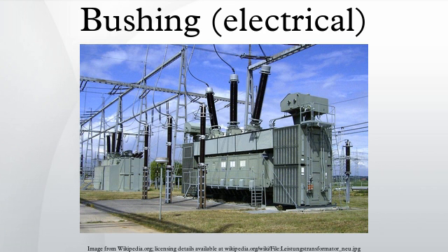The inserted conductive foils produce a capacitive effect which dissipates the electrical energy more evenly throughout the insulated paper and reduces the electric field stress between the energized conductor and any earthed material. Condenser bushings produce electric stress fields which are significantly less potent around a fixing flange than designs without foils and, when used in conjunction with resin impregnation, produce bushings which can be used at service voltages over 1 million volts with great success.